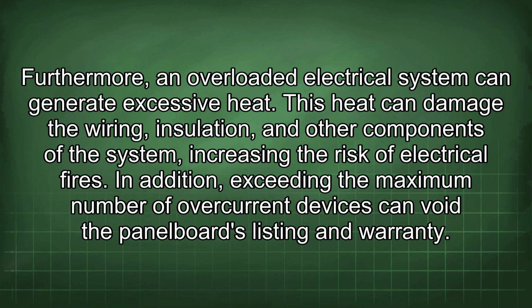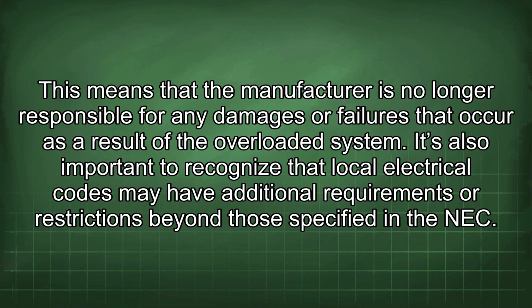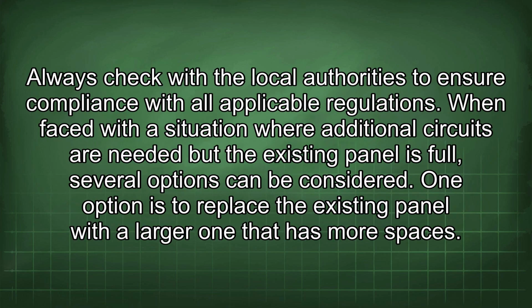In addition, exceeding the maximum number of overcurrent devices can void the panel board's listing and warranty. This means that the manufacturer is no longer responsible for any damages or failures that occur as a result of the overloaded system. It's also important to recognize that local electrical codes may have additional requirements or restrictions beyond those specified in the NEC. Always check with the local authorities to ensure compliance with all applicable regulations.